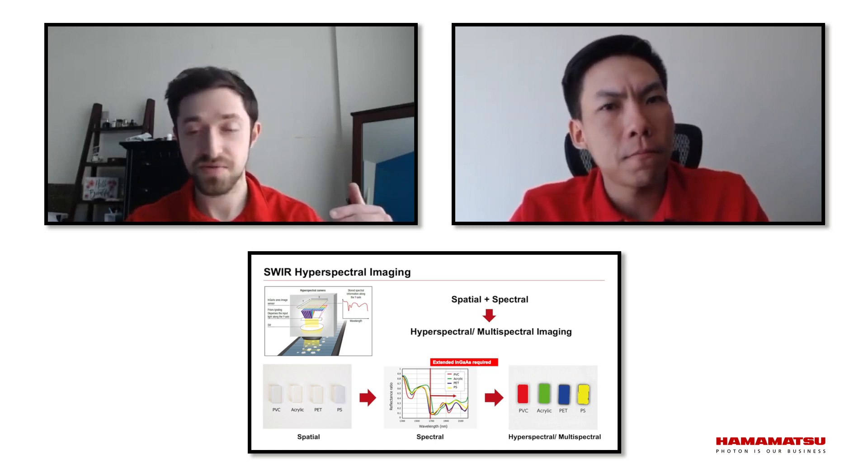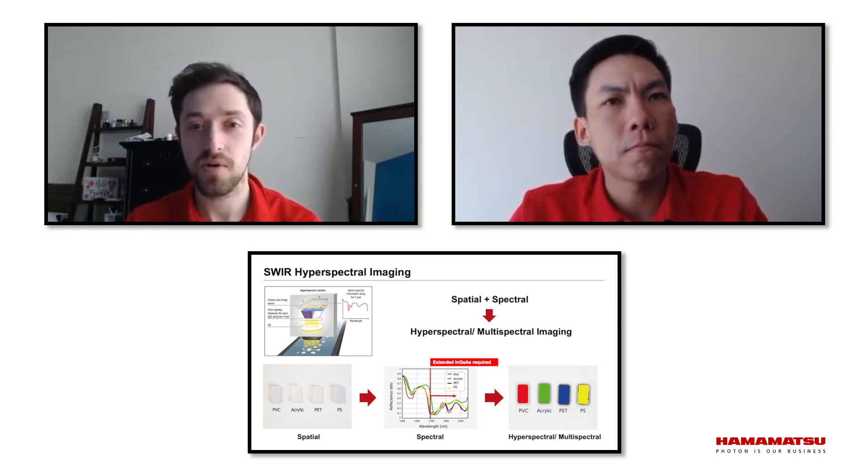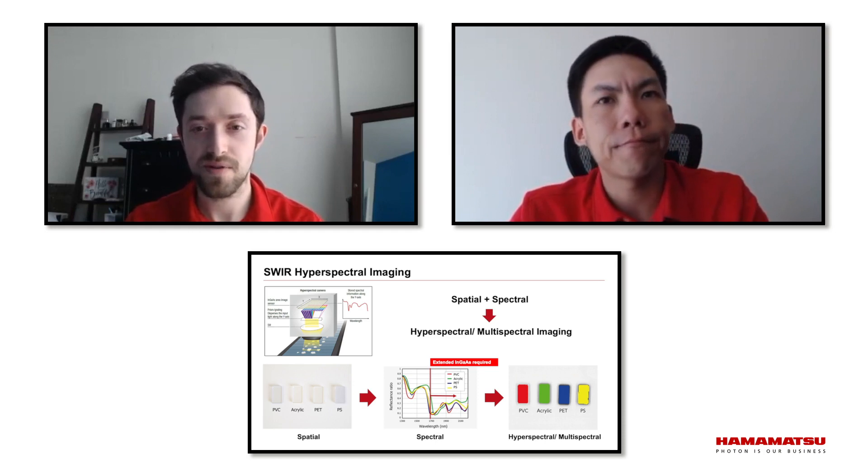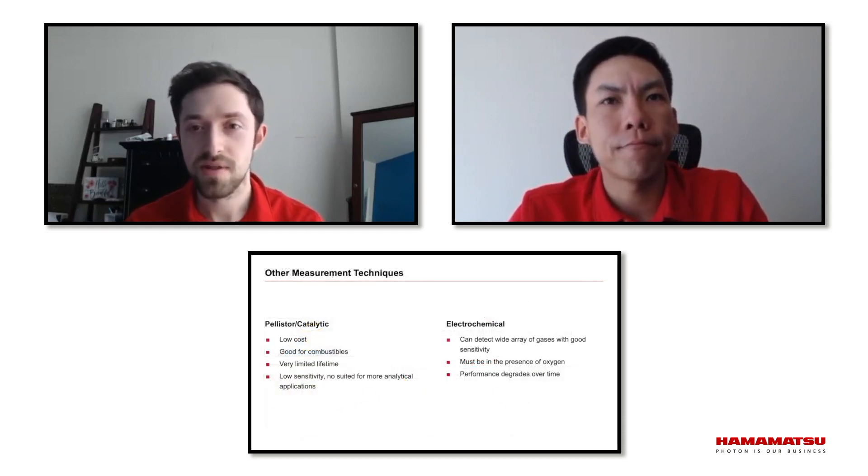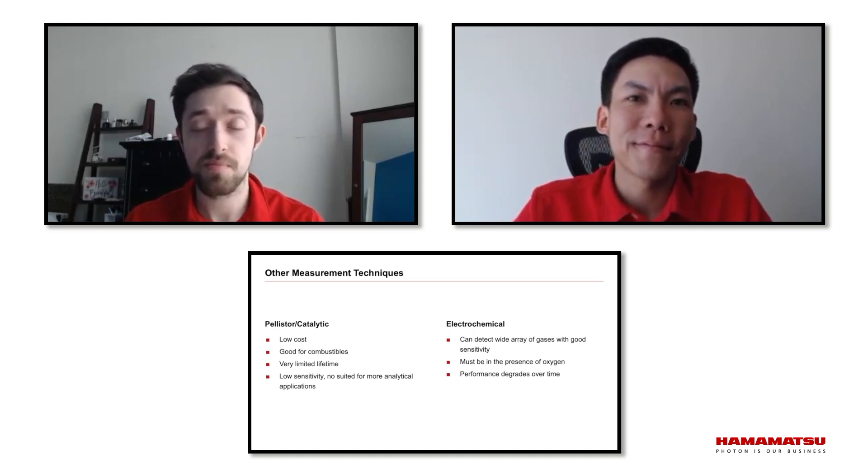Yeah, absolutely. So, I run into gas analysis all the time. And I really like the mid-infrared for several reasons. But first, I want to give some background. There are several ways to go about gas analysis. There are pellistor and catalytic detectors that rely on a chemical reaction. There's electrochemical, which is kind of similar. A substrate reacts and creates electrical signal. The thing about those is the pellistors and the catalytics are very cheap, but they do not last very long and they aren't too sensitive. Electrochemical can provide a lot of sensitivity across many compounds, however they degrade over time, and also can be quite finicky with environmental conditions and also need oxygen.